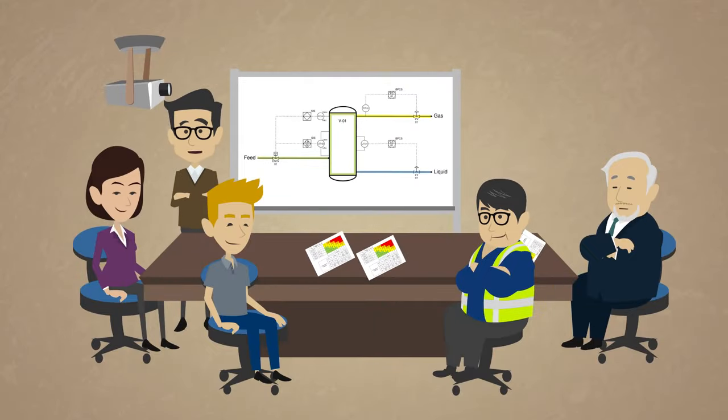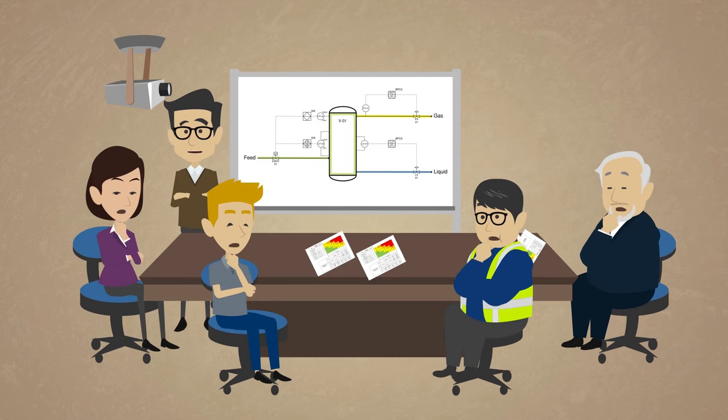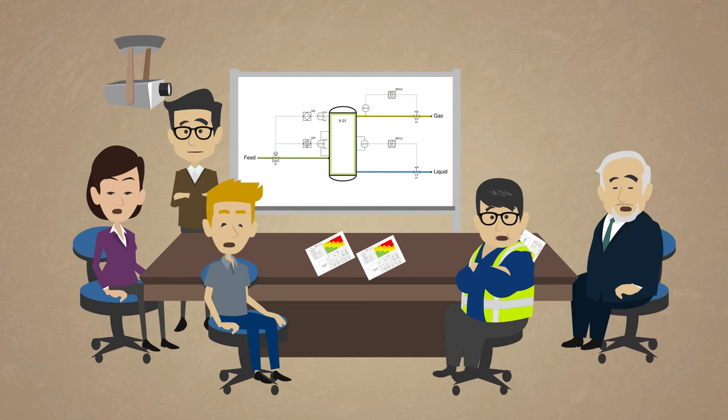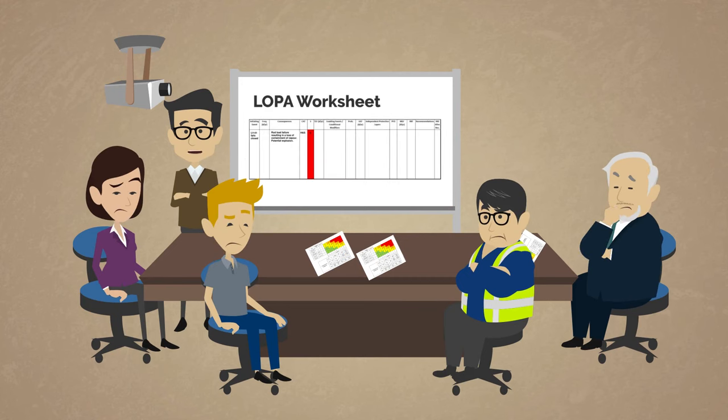This would result in a potential catastrophic rod load failure of the compressor, causing a significant loss of containment of vapor, with the possibility of a vapor cloud explosion and potential fatality. Let's jump in to the LOPA.